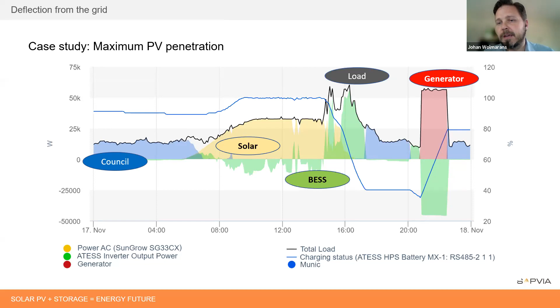So we had a small reserve that we can then draw upon immediately and run off for a short while. And once we reach the second limit, that's when we start the diesel gensets, and that'll pick up the building load. We'll run the generator as efficiently as possible to charge up the battery, not all the way, but to a preset limit, so in this case, 80%. And after that, council power returned, but the battery was also charged sufficiently, and we switched back to municipal, to council power.